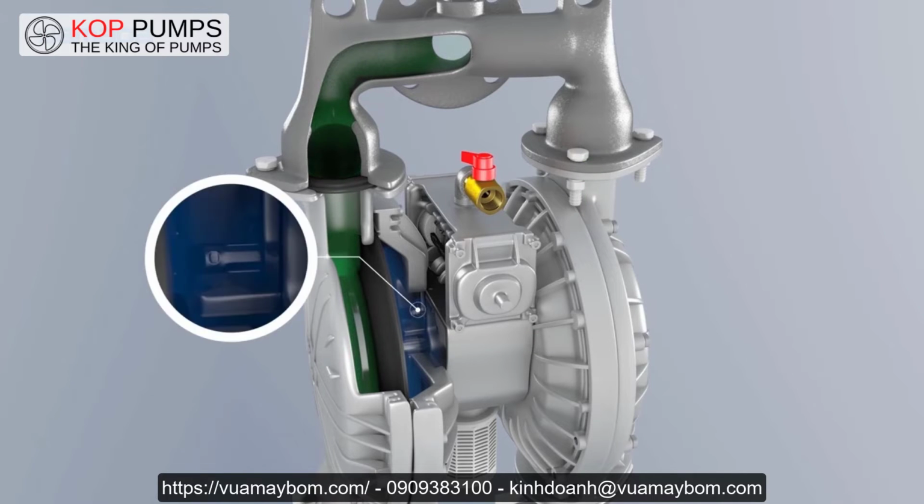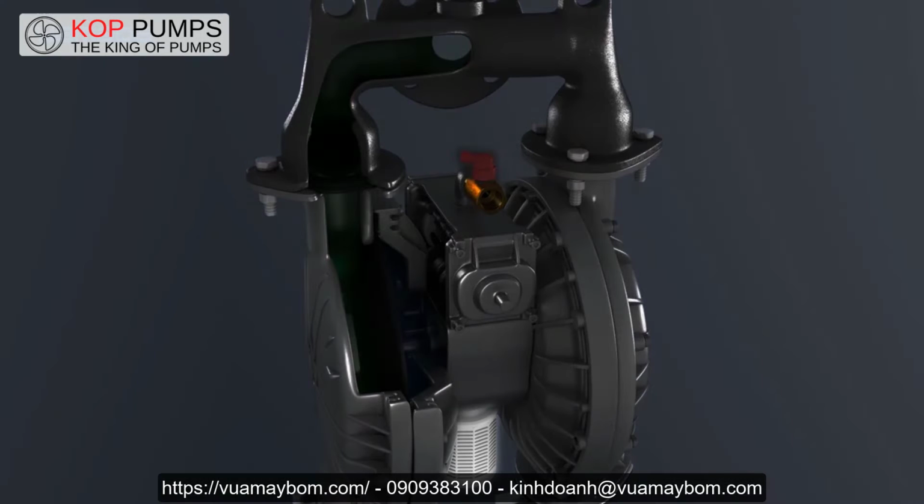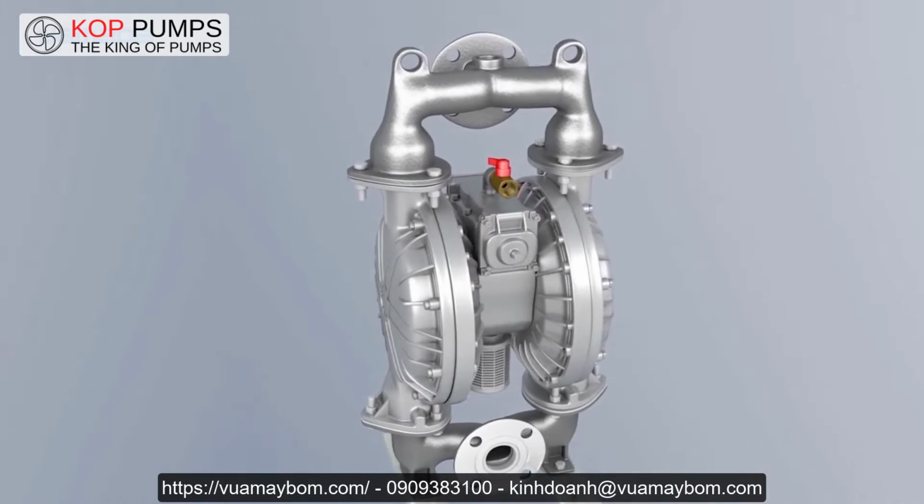When it travels a full stroke, it will contact the pilot valve, depressing it and breaking the seal to open an exhaust port. The open port allows compressed air to exhaust from the backside of the air valve. The pressure drop produces a shift of the main air valve. This motion simply repeats on the other side.